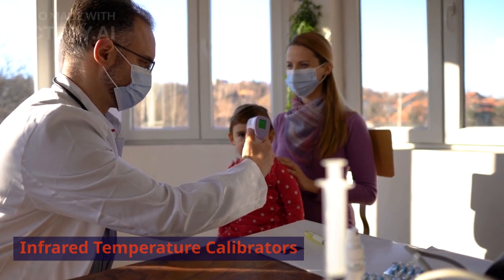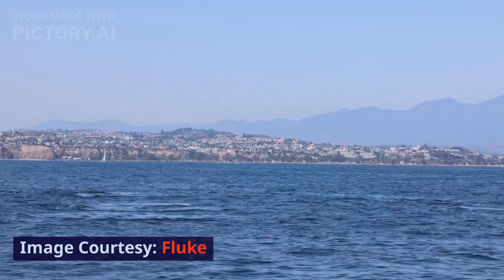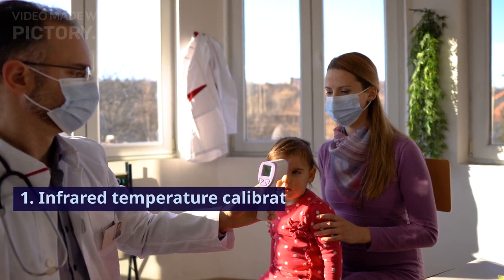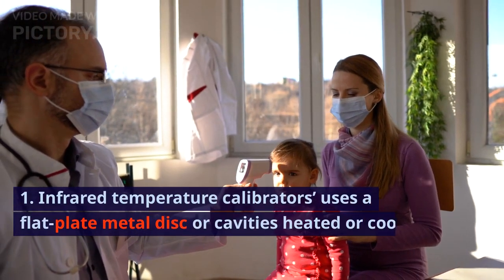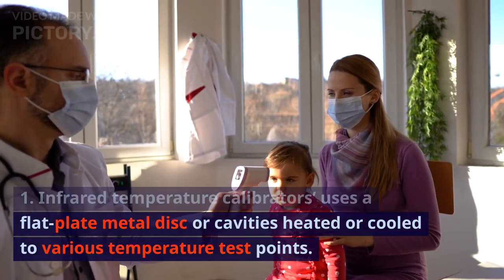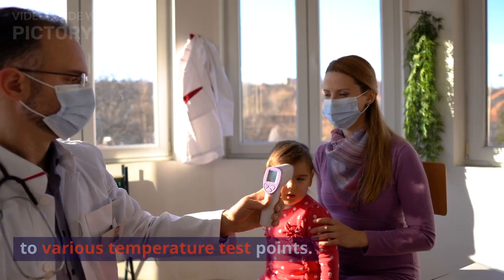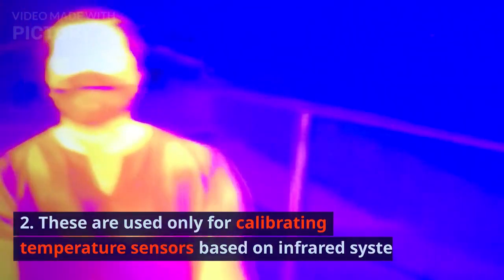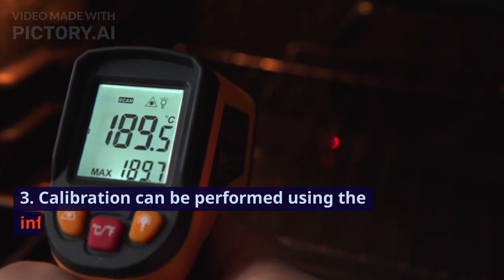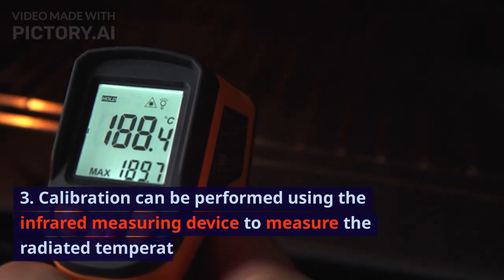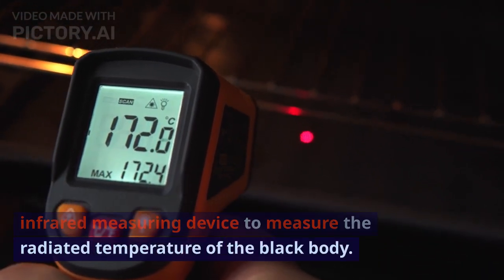Infrared temperature calibrators. 1. Infrared temperature calibrators use a flat plate metal disc or cavities heated or cooled to various temperature test points. 2. These are used only for calibrating temperature sensors based on infrared systems. 3. Calibration can be performed using the infrared measuring device to measure the radiated temperature of the black body. 4.